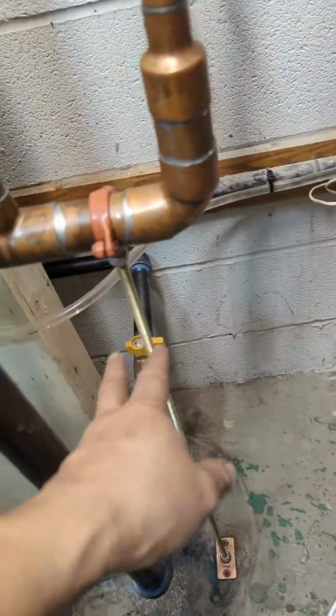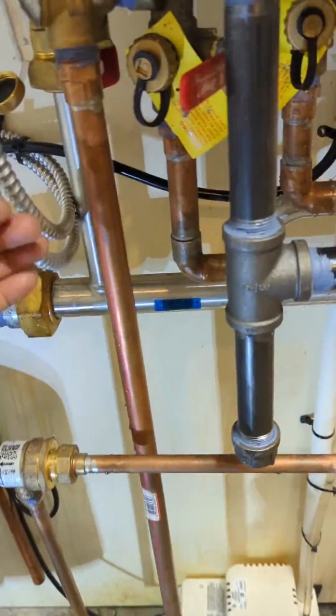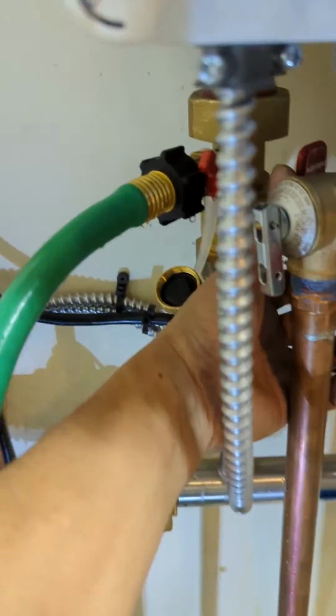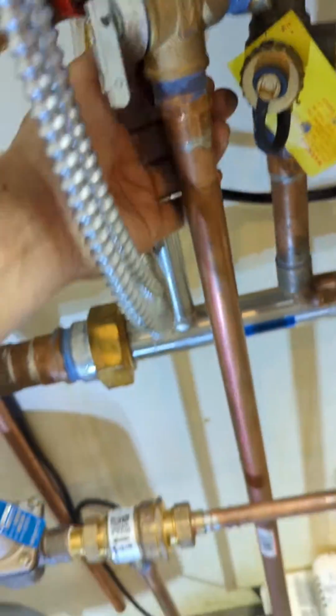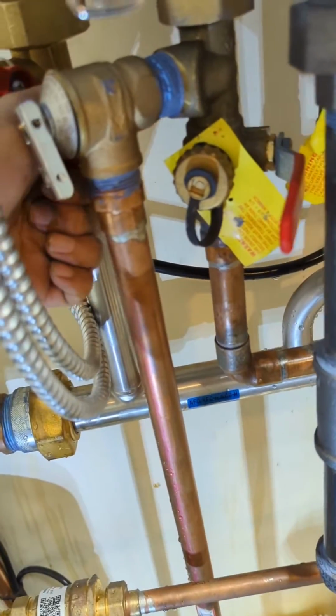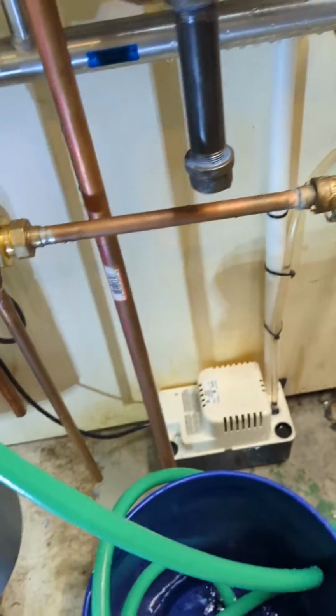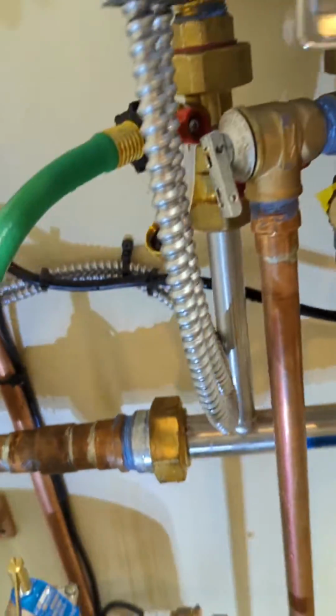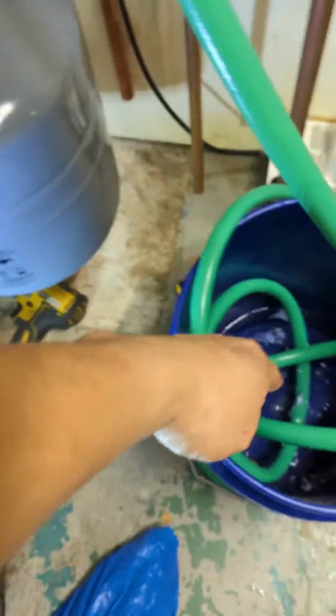So we have to shut this down. I still have the gas off, that way it's not going to kick on. Then I'm just going to shut off the supply side, that way I can force the air to go out to this side. So by stopping it here, it will come out to here.